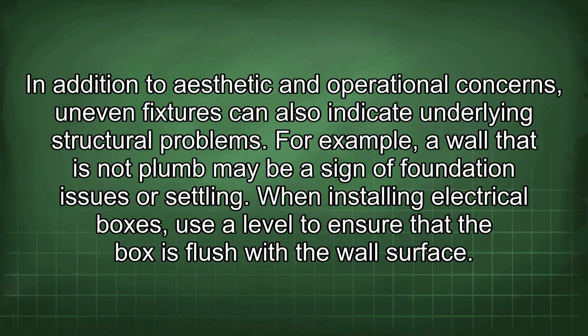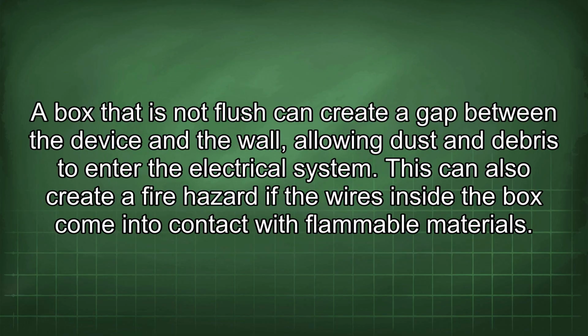When installing electrical boxes, use a level to ensure that the box is flush with the wall surface. A box that is not flush can create a gap between the device and the wall, allowing dust and debris to enter the electrical system. This can also create a fire hazard if the wires inside the box come into contact with flammable materials.